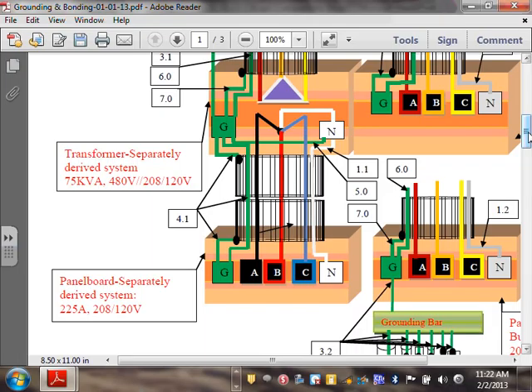And you get yourself, what was the size here? That was number 2, based on the conductors coming out of the transformer, not coming in. A lot of people size it sometimes based on the conductors coming in. No, these are based on the conductors coming out. Any comments, guys? Any questions about that?